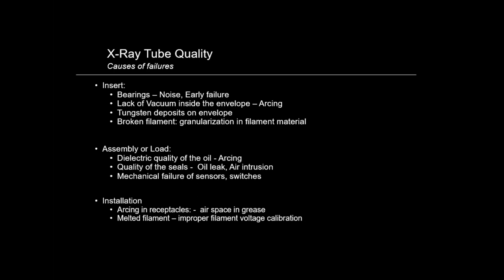So the reason X-ray tubes fail are bearings. They can be noisy and not necessarily fail, or noise can be a sign of early failure. If you don't have a good enough vacuum inside the envelope, it can cause arcing. Sometimes a new tube, they'll say you need to season it and get a few arcs out of it. By warming that tube up, you'll clean out the additional molecules in the vacuum and make it more stable. You can get tungsten deposits on the black envelope, which actually creates a shortcut for arcs. You can have a broken filament in the filament material. These are typically manufacturing problems.